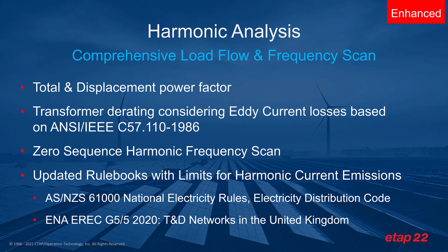The harmonic analysis now includes the ability to give you total and displacement power factor, transformer derating, which is considering the eddy current losses based on ANSI C57, zero sequence harmonic frequency scan, and updated rule books with limits for harmonic current emission that's used to alert or inform you that you are exceeding these limits at the point of interconnection. And these new rules have been added based on Australian standard 61000 as well as ENA G5/5 2020, which is the emission limit for United Kingdom. So let's see a few of these in action within ETAP.